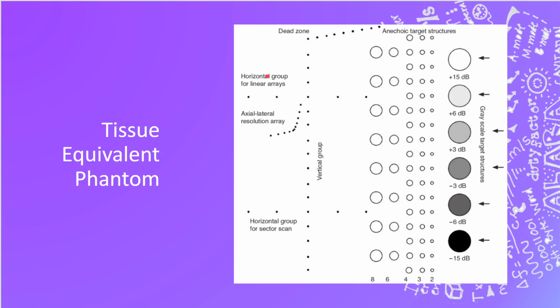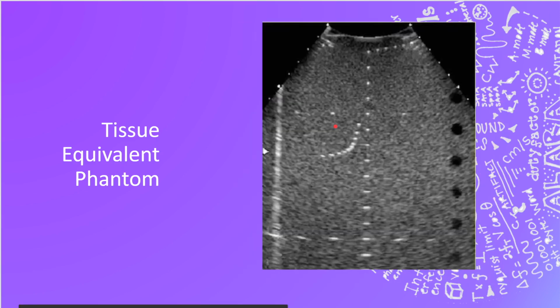The vertical group here shows us, can we register echoes all the way through the vertical portion of the image? It also tells us, can we register the appropriate distance between each of these dots through the vertical part of the image? And the other thing you'll see, I'm going to jump back to the picture prior. On that vertical part, we can see really thin dots up at the top here.